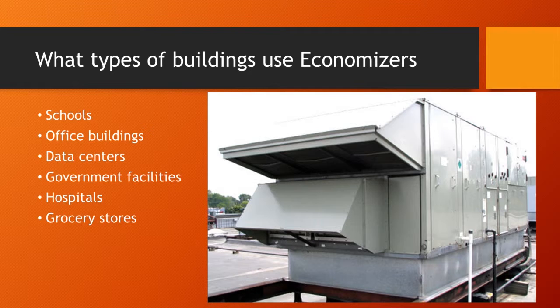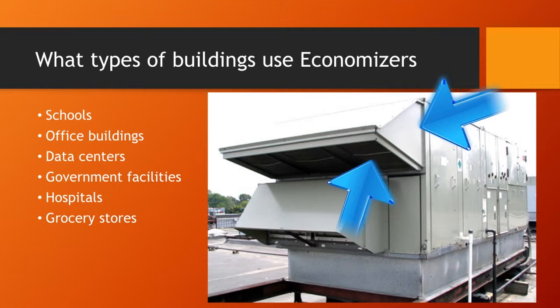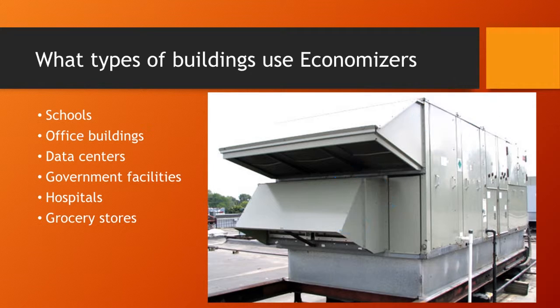Here's an example. You have a large rooftop unit here. This is your rain hood covering the area where the outdoor air is going to be going inside the unit. Has fins connected to actuators. That's going to be used with controllers to modulate how much outdoor air you're pulling inside that unit, going through the filters, sucking in with the fans through your supply air ducts.